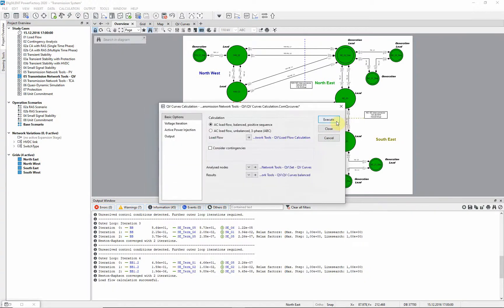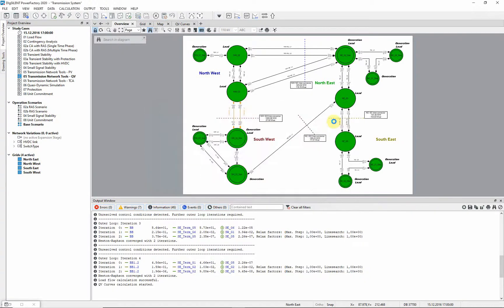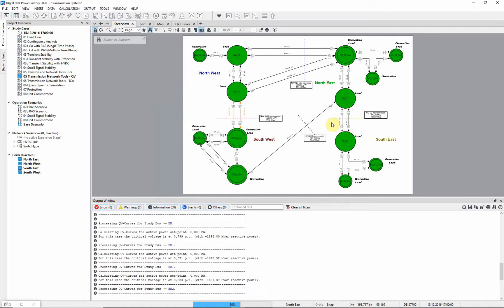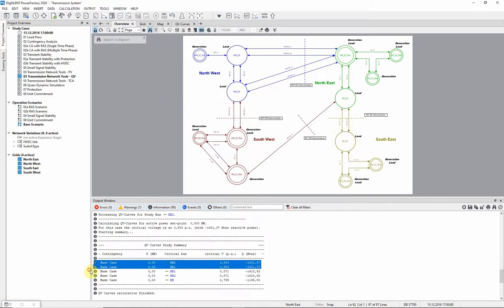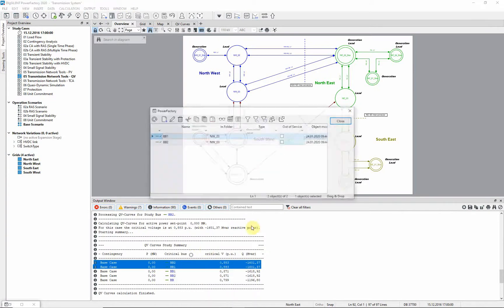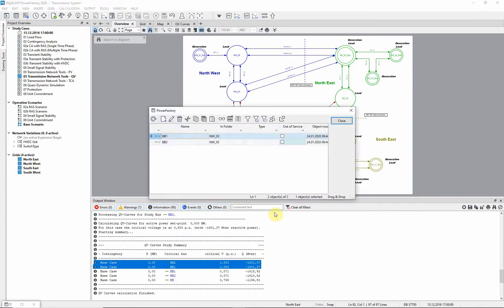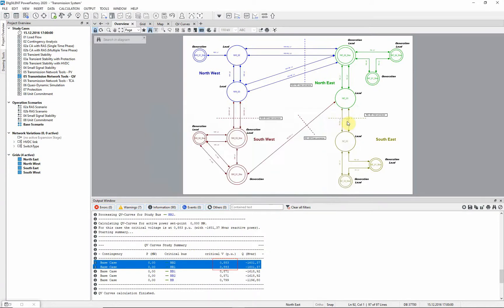Then we press execute to start the calculation. In the output window, we can see that the two most critical busbars are these two, which are at substation NW03, and the critical voltage is 0.883 per unit.